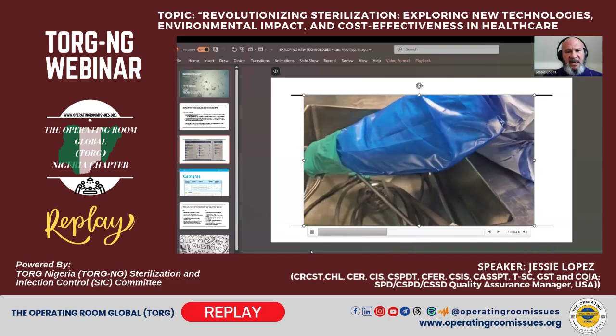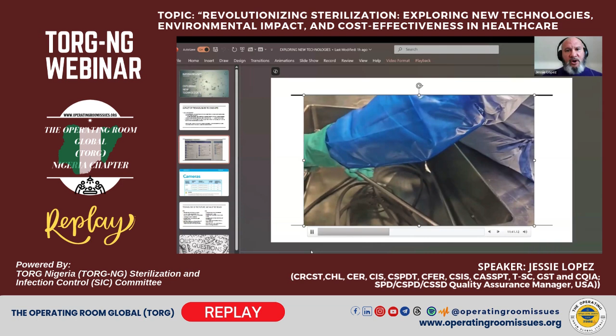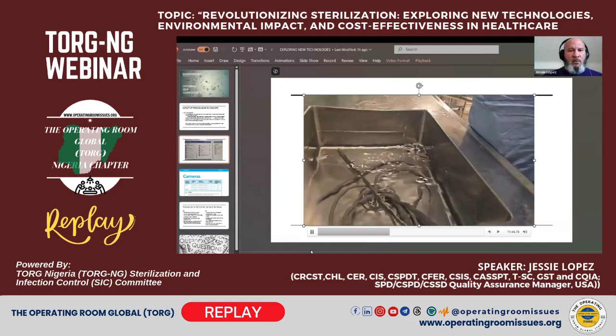So we're going to utilize a pressurized water pistol. There are 2 sections of this joint that need pressurized water for 30 seconds each, 30 seconds for each section. Once we've pressurized, we are now going to brush these surfaces and wipe off with a sponge. This portion of the IFU is to remove the detergent off the surface of the device.